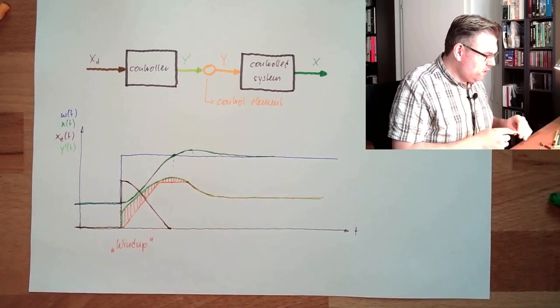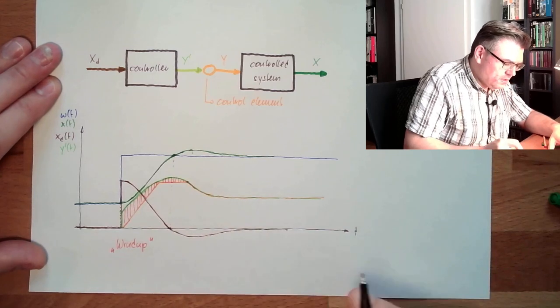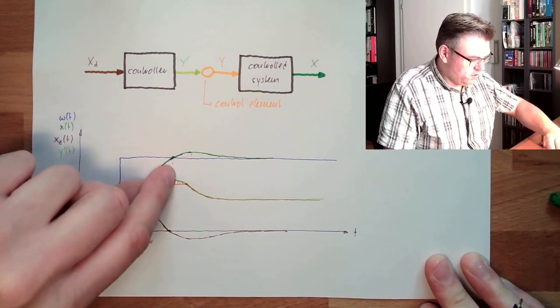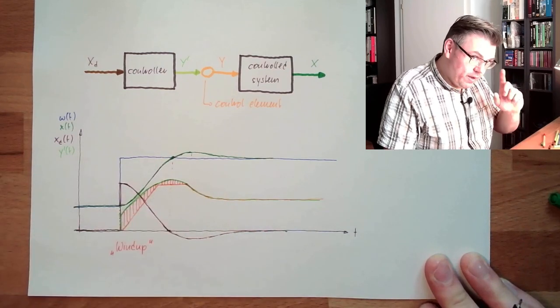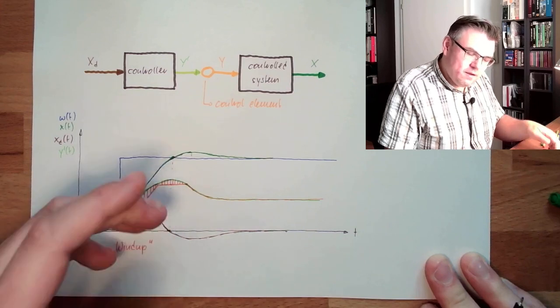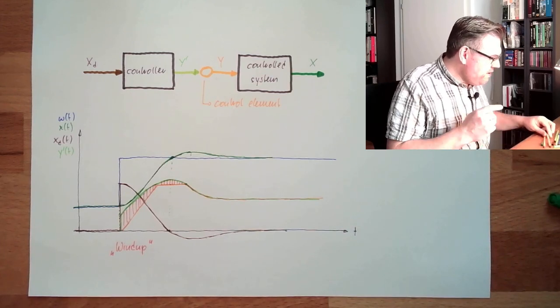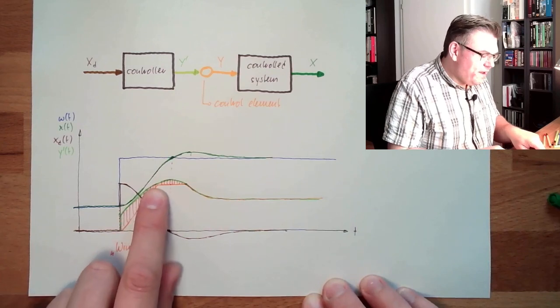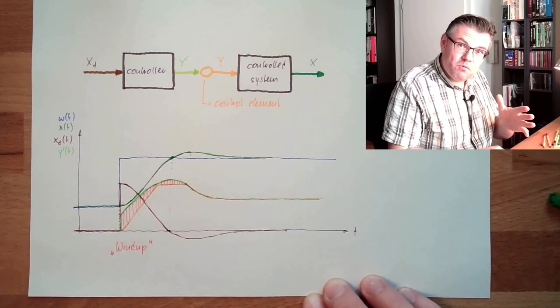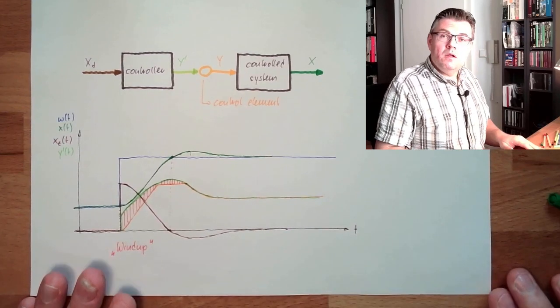For the proportional part, this is no issue. The proportional part is mainly a gained difference - here, the proportional part is already zero at this point in time. However, the I part, the integrating part, is too high. Simply because it was already too much from the beginning. Even if we could follow up with our control element, even if it is fast enough, we would still see this because there is somewhere a maximum power. And the internal correcting variable might overshoot.